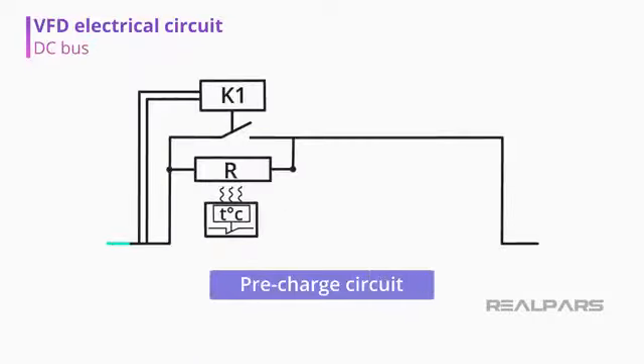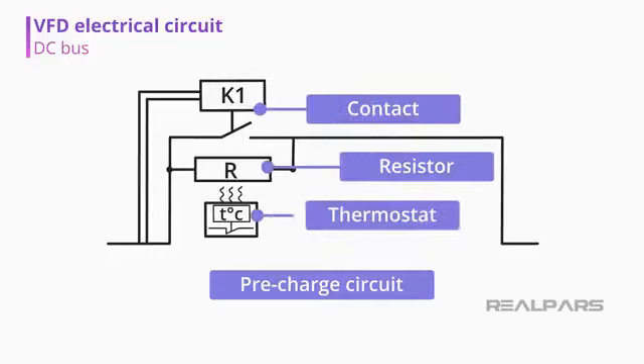Pre-charge is a current limiting circuit that slows the charge rate of the bus capacitors during power-up. The pre-charge circuit shown here is composed of a contact, a resistor, and a thermostat.